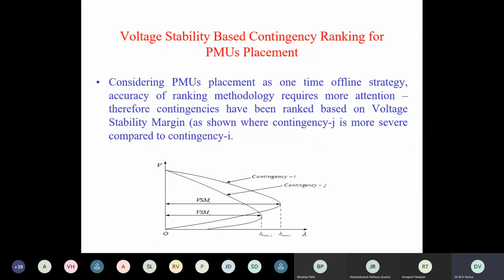So for voltage stability, he considers different contingency line outages. For that he obtains the contingency ranking based on voltage stability margin. What is voltage stability margin? It is the distance between the base case operating point and the nose point. So this is the voltage stability margin for contingency I, and this is the voltage stability margin for contingency J. Contingency J has a lower voltage stability margin, so it was considered more severe. So based on the voltage stability margin, you identify critical contingencies. And for these critical contingencies, he did observability analysis based on PMU placement.